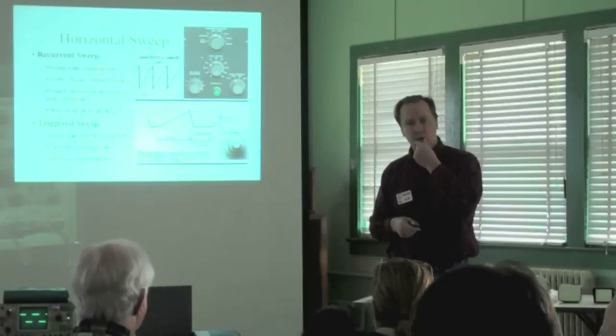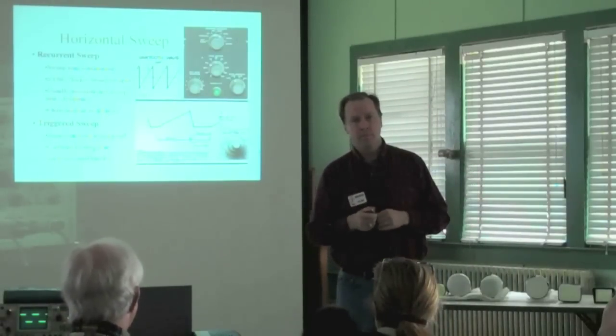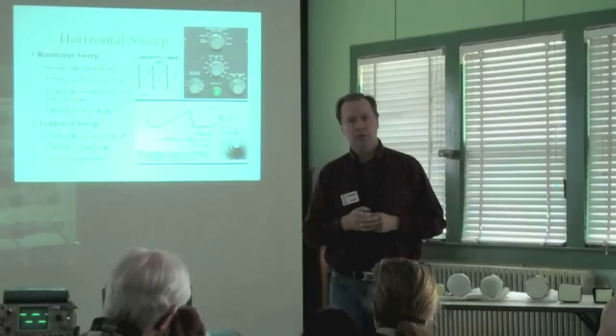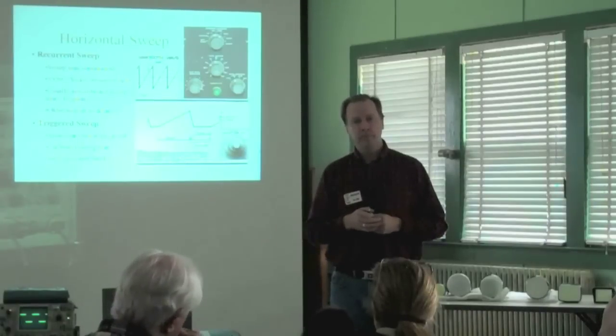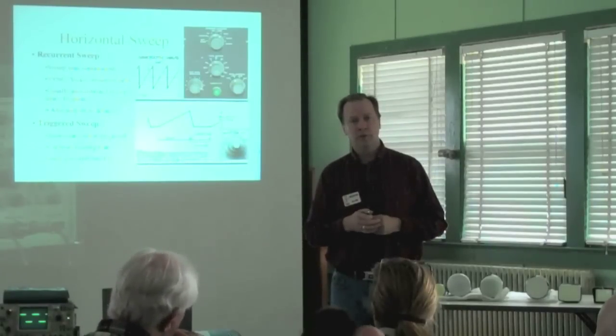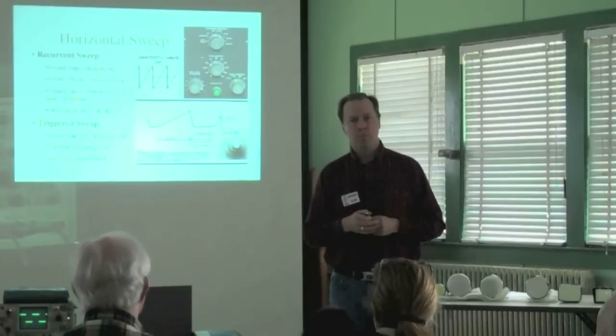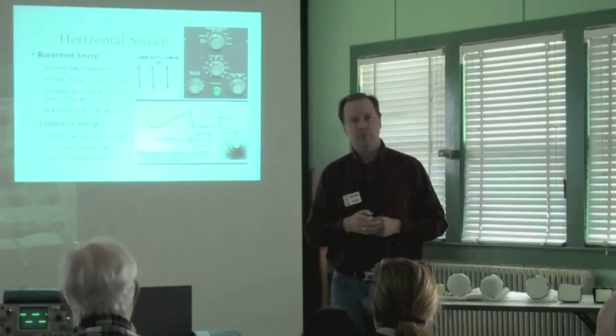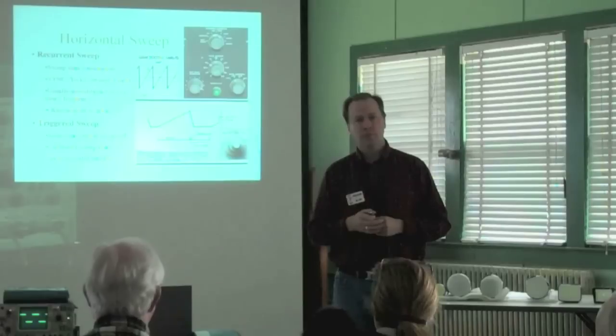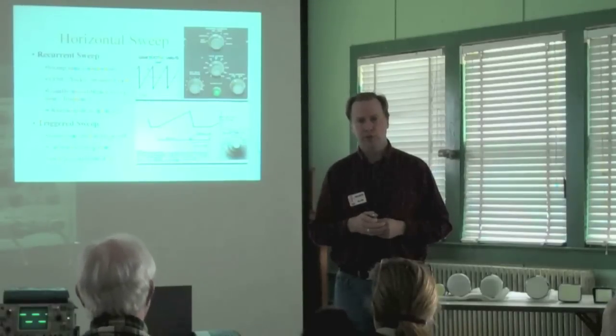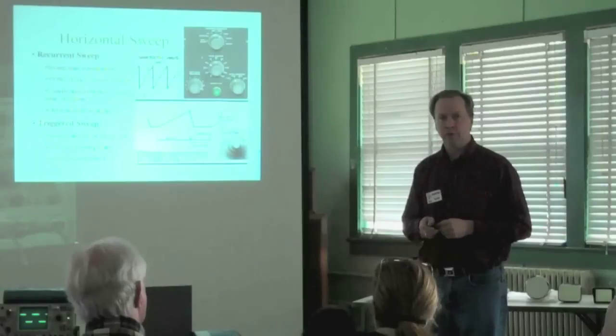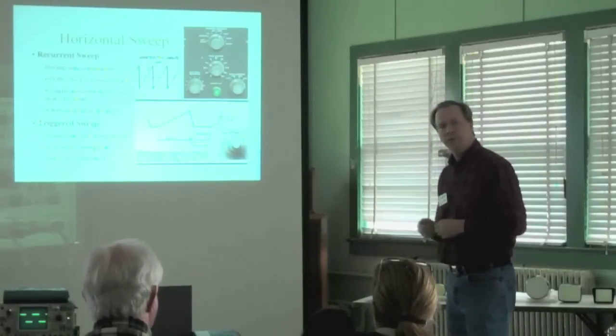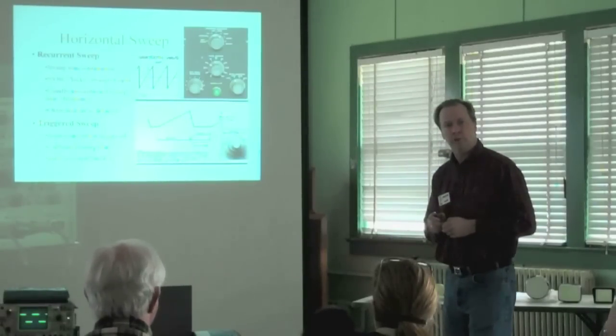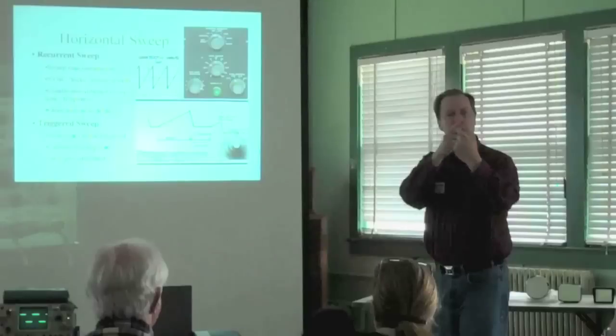When you get back to that sweep time per division control for a second, remember what you said about the inner pot, you could adjust, it's almost like ignoring the fact that you have a trigger scope and you're just kind of looking for waveforms and wave shapes. What I'm saying is that adjustment, is it irrelevant to the setting of the sweep time per division? Yes, it is. In other words, if you've got the pot off of the detent where it's switched off, then you're not using that sweep time per division control. You're somewhere between it and the lowest value.